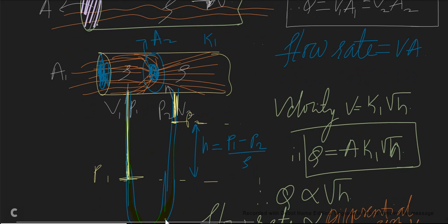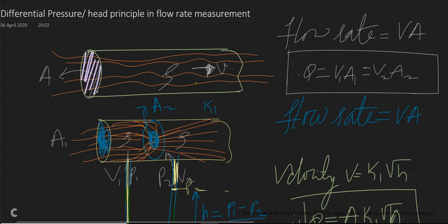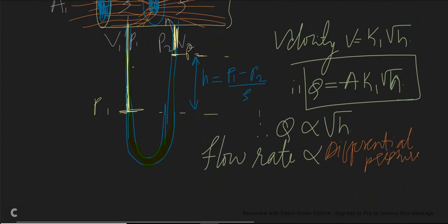Using a pressure tube containing a fluid connected between the two sides of the pipe: in a plain pipe without obstruction the fluid levels would be equal, but here the pressures differ. The fluid in the tube moves from the high-pressure side until equilibrium is reached where the other side's pressure stops it. The difference in levels is measured and is the loss in head, indicated by H, given by H = (P1 − P2) / rho. This gives us the differential head or differential pressure.